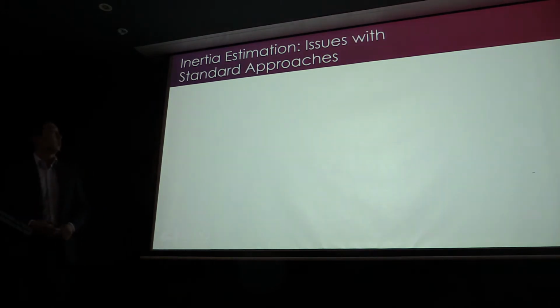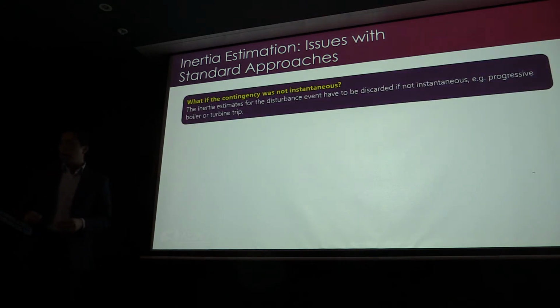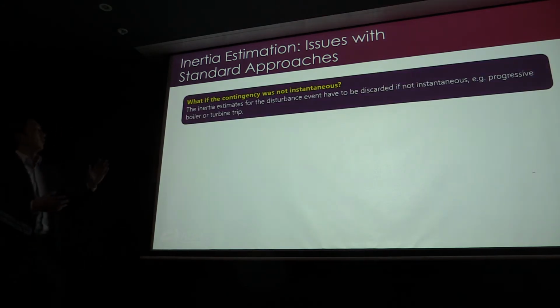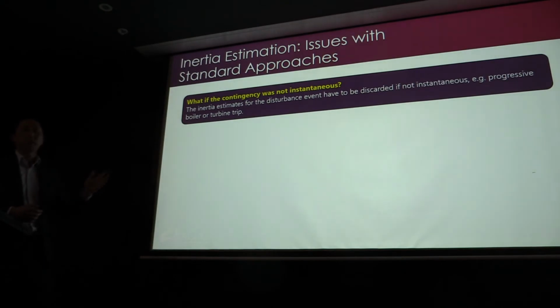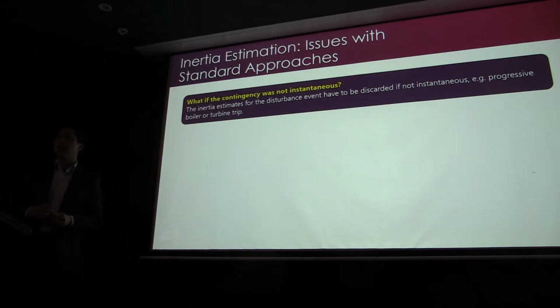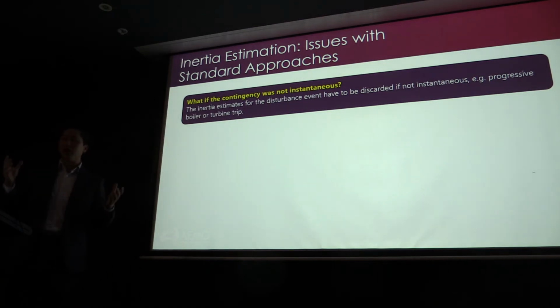However, there are some issues with the standard approach. First of all, let's talk through some of the issues. What if the contingency is not instantaneous? You have to just discard that event. So if you had a boiler trip, for example, that just ramped down and failed, then you basically can't use that event in an inertia estimation, because what you'll end up seeing is a roll-off that's very slow. And then when you start plugging that roll-off back in, you'll see inertia that's very, very high. And so that's clearly wrong.